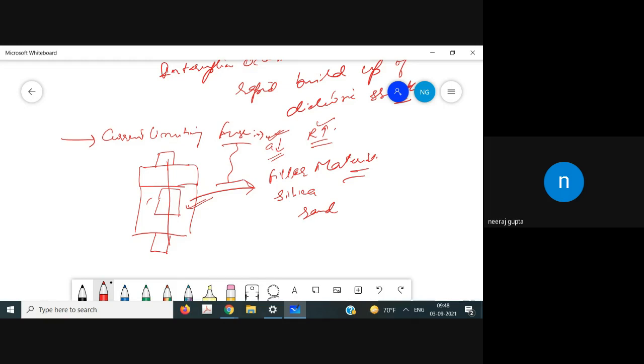So in the case of the current limiting fuse, we restrict the arc to a particular area by using the filler material, thereby limiting the current. We decrease the area of the cross section, and as a result the resistance increases and the arc doesn't restrike.